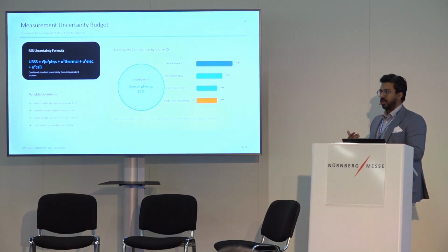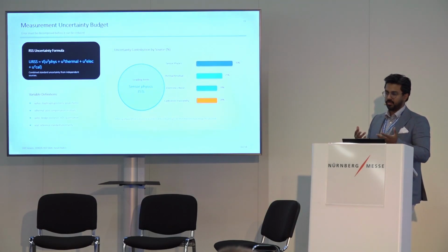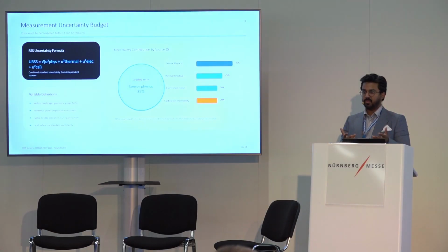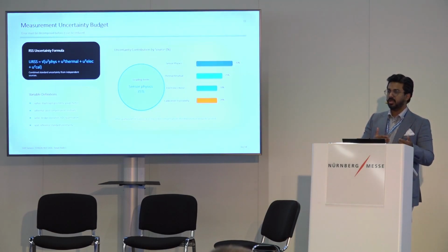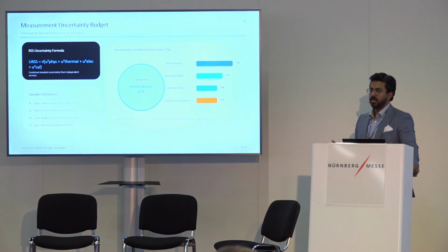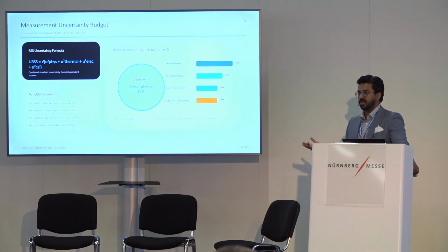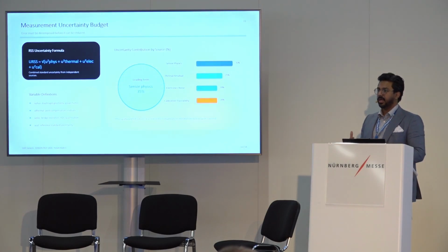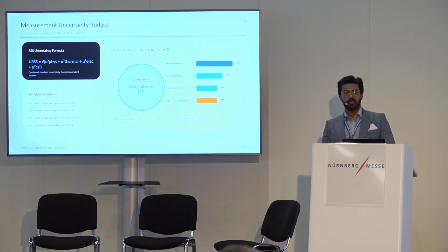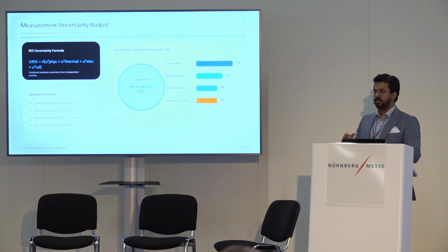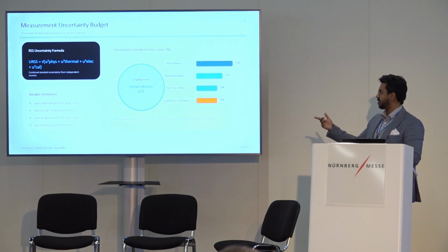It's very normal that when we are vapor depositing the thin film on whatever substrate we choose, there would be an error percentile, and that is where the sensor physics and the gauge factor will not be the same for every sensor. It might be a bit different. Of course, we try keeping it at the same stage, but it changes to a certain degree. So if that happens, what do we do? We don't throw out the sensor. We want to optimize the results in later stages of manufacturing.